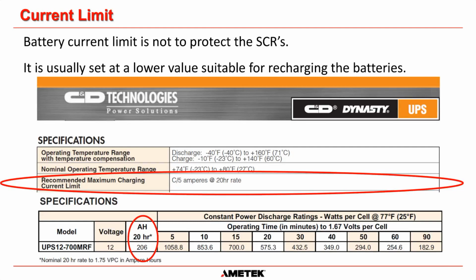What is the effect of connecting new batteries in series with old batteries that are still more or less healthy? As long as the new batteries are charged as per the manufacturer's guidelines before they are put into the string, then there should be no problems. Obviously, you don't want to introduce a whole load of new batteries into a string that has old batteries, because those old batteries are eventually going to fail as well. But there is no effect as long as you make sure that the new batteries have been charged up correctly. Because if they're not charged up correctly, then they will want more current to get charged up, and that will draw current through the other batteries that don't need that current, and will cause an imbalance in voltage across the string.